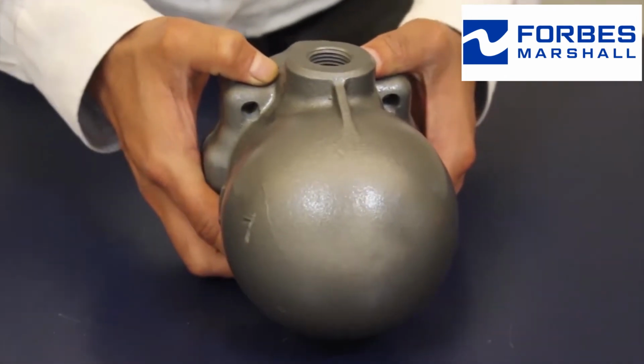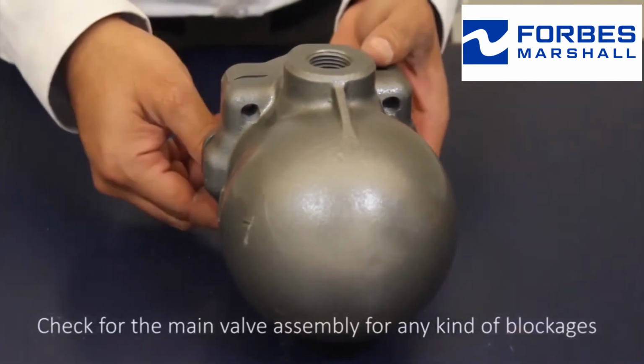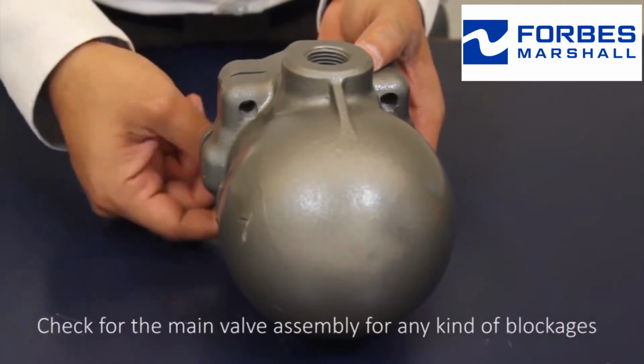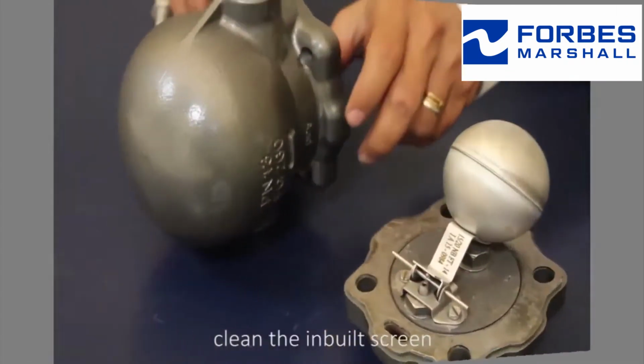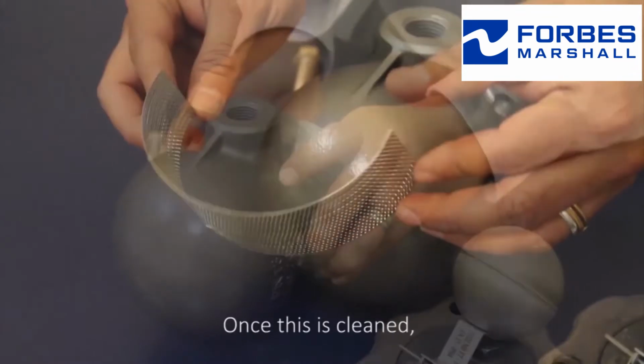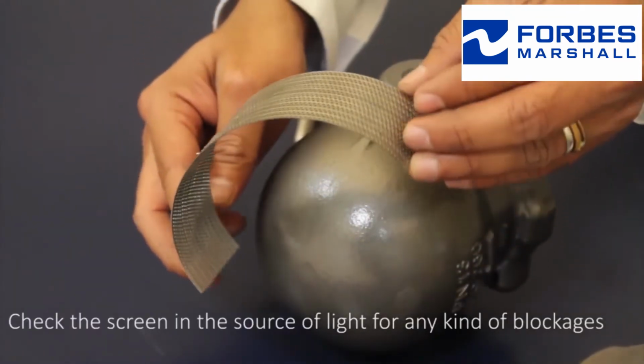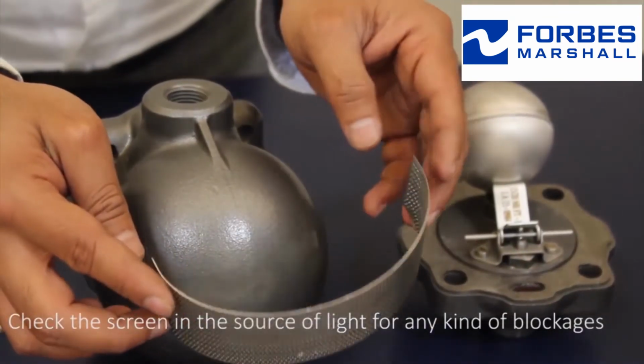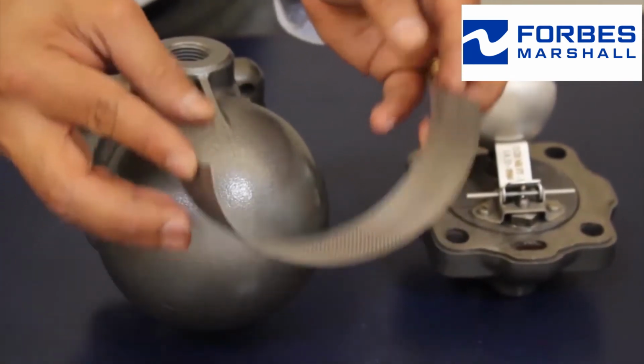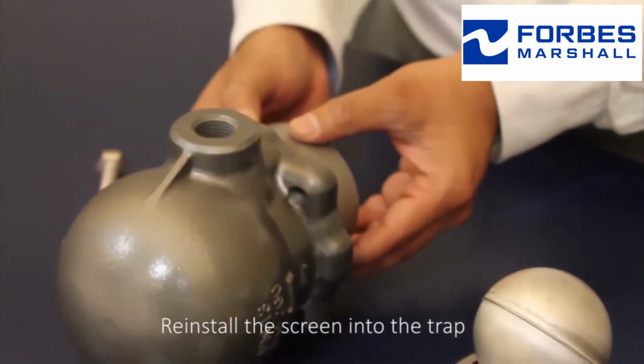Once this is checked, check the main valve assembly for any kind of blockages. Clean the inbuilt screen. Once cleaned, check the screen in the source of light for any kind of blockages, then reinstall the screen into the trap.